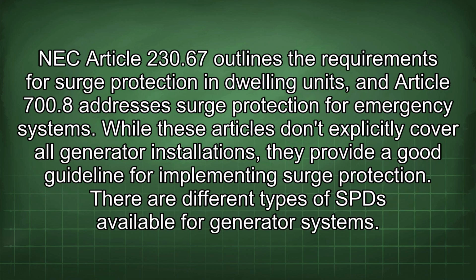NEC Article 230.67 outlines the requirements for surge protection in dwelling units, and Article 700.8 addresses surge protection for emergency systems. While these articles don't explicitly cover all generator installations, they provide a good guideline for implementing surge protection.